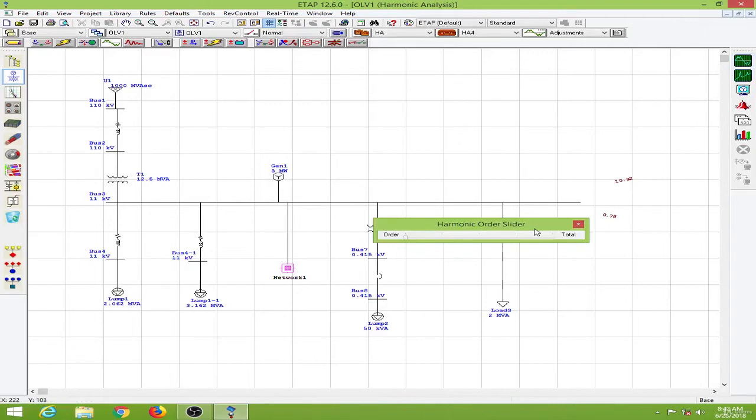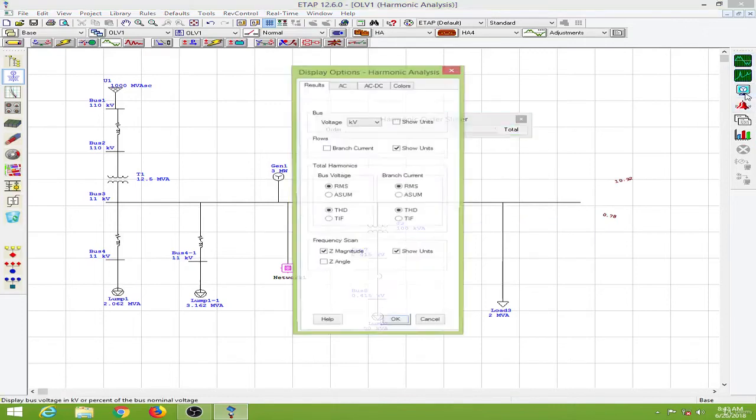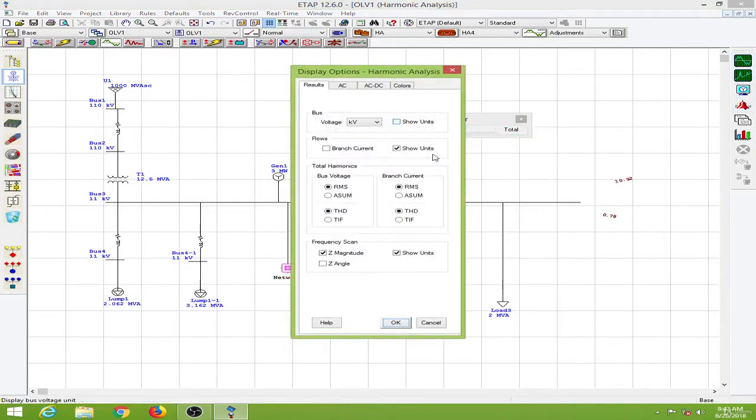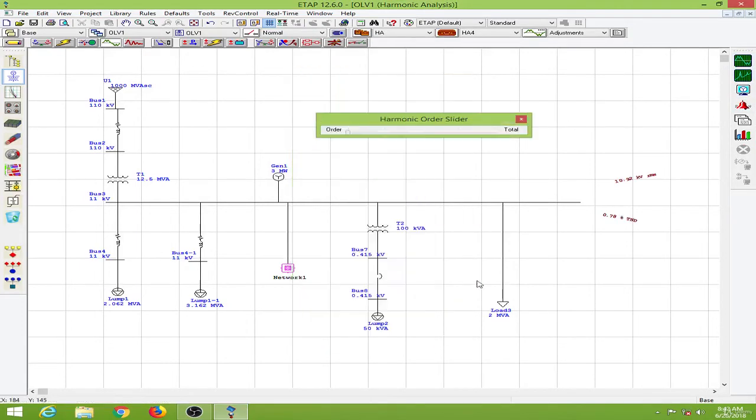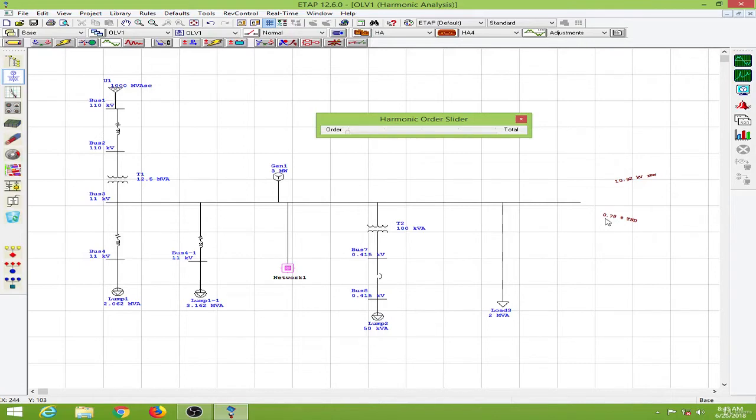And again run this. And go to my display options. Okay. This is the fundamental harmonic or the first harmonic, which is occurring at 60 Hz. So this is about 10.92 kV. And the total harmonic distortion is given in percentage is about 0.78%.